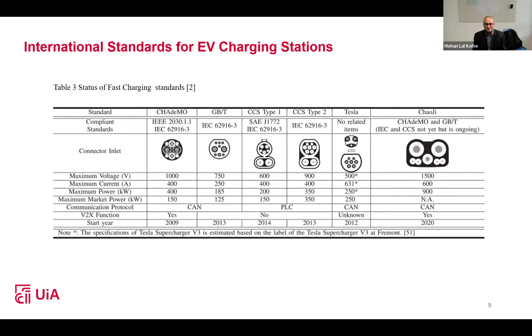So let's say if I take Tesla Model 3, with its range of 450 kilometers and charging power available, let's say 250 kilowatt. To charge from state of charge 20% to 80% in 15 minutes, we are going to require for Tesla Model 3, within that time, a 250 kilowatt demand.